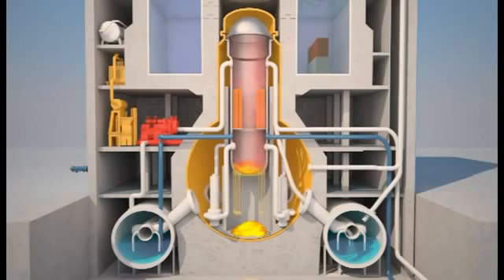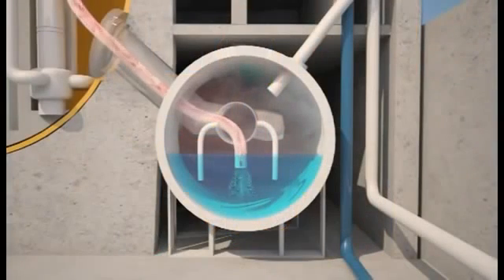As the steam pressure rose to a dangerous level in the reactor vessel, the depressurizing valves opened. Gas was forced into the wet well suppression pool by a venting line. The water acted as an efficient filter by trapping much of the radioactive elements.